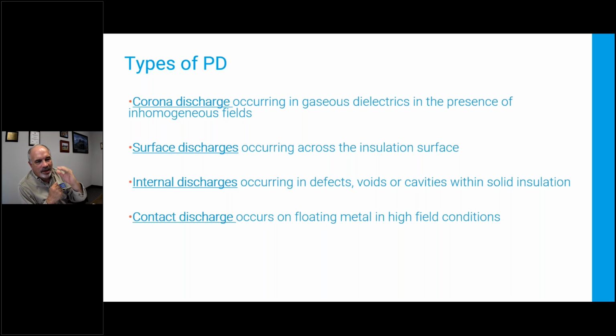You use different techniques to detect them, but you need to understand them both. The last is contact discharge. This is where I have metal in the high voltage field. And that metal is going to give me a bit of a problem in that it is highly conductive. It acts like a perfect discharge source. But again, you're not going to damage insulation with this, so it doesn't lead to catastrophic failure. But because it creates such a high signature, it can hide surface discharge and internal discharge that might be lower level, and that is a concern.